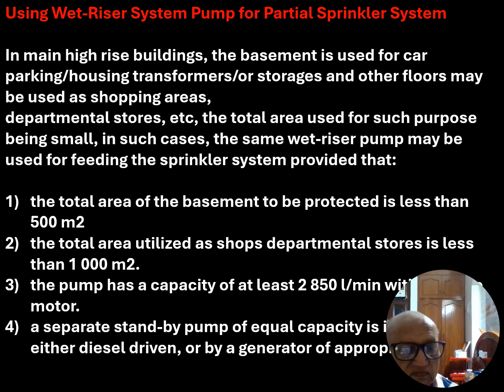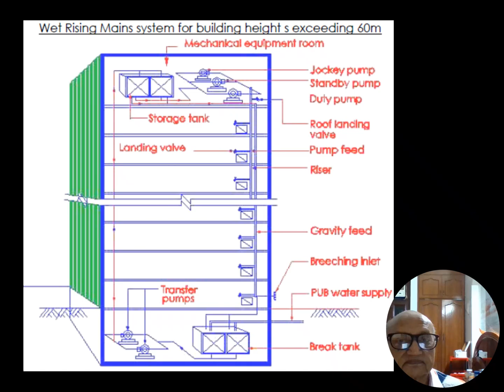Friends, engineers and architects, this particular slide demonstrates a wet riser system for buildings with height exceeding 60 meter. In high-rise buildings, if the height is exceeding 60 meter, there is a practice of providing service floors after a certain number of floors. And these facilities are provided in that system. Friends, this slide on wet riser provides the design features of the wet riser.